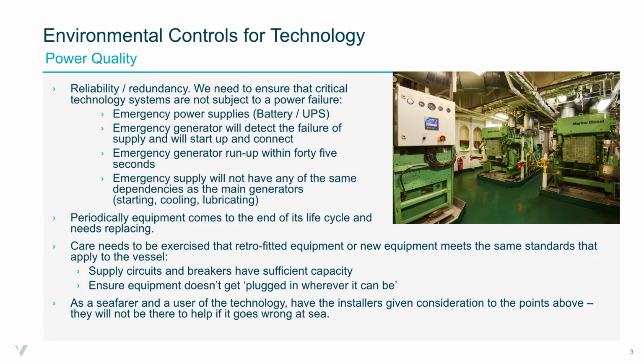and emergency generation on board will have none of the same dependencies, so the emergency generator will have independent starting, compressed air. It'll have independent cooling and lubrication so that it can run in the event of failure of one of those systems in the auxiliaries. So you've had a failure caused the generators, the main generators to stop. The emergency generator won't be subject to the same dependencies, so it will be able to provide that emergency power.